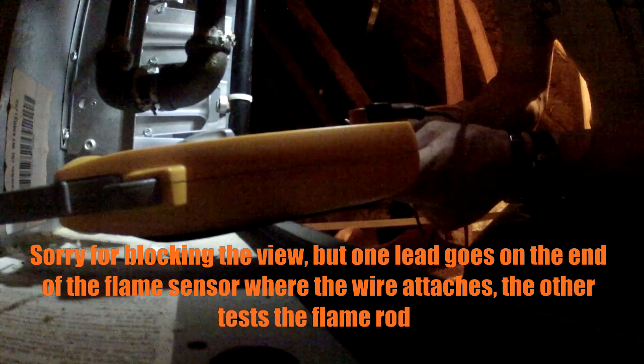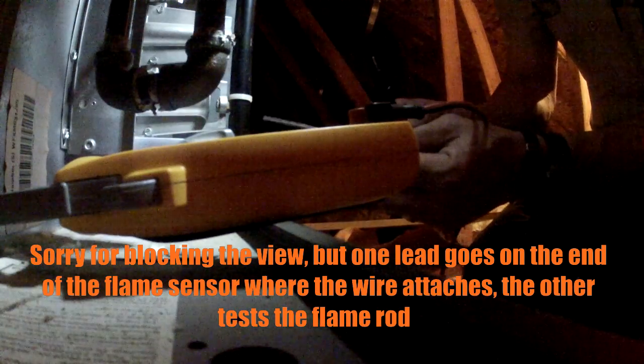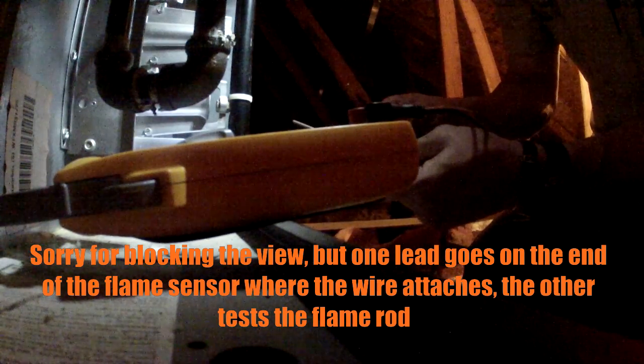Okay, so here's a quick way to check your flame sensor, just like on a maintenance, or in this case, I just want to quickly see what kind of shape it's in. I'm looking for continuity throughout the whole flame sensor. I'm going to put one lead on one end and just listen to the beeps. If it's solid, like this, then I got really good connection and the flame will be sensed easily. If it beeps, you know, beep here, beep there, then I don't have a consistent flame rectification.